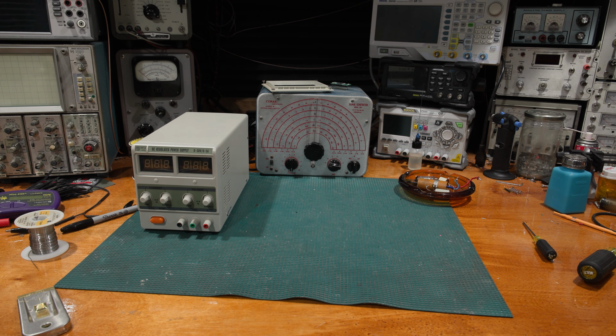This is really convenient for calibrating an RMS source, as we can use a thermal transfer standard, which is a very accurate thermal component that takes the AC and converts it to heat. The heat is then measured and, through a calibration, outputs a DC voltage that we can then measure very accurately. That is what the Ballantine does. So the Ballantine 1600 is an automatic thermal transfer standard. There is a Fluke version, which I might add to the lab as well.